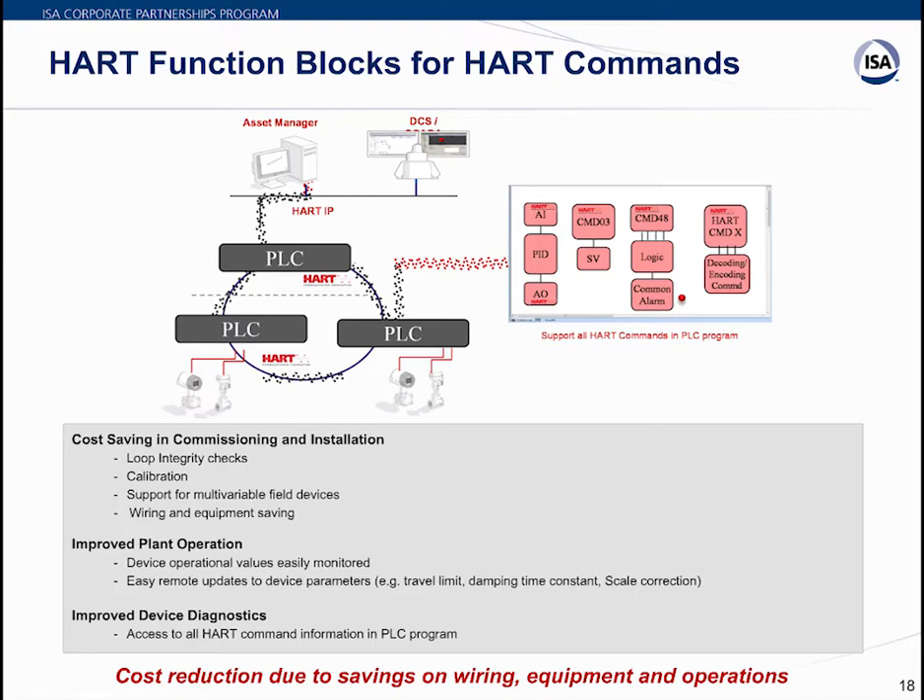Plant operations are significantly improved with HART command support in the PLC. It allows easy remote updates to device parameters — such as travel limits for control valves, damping constants, or scale correction on transmitters — without needing an asset manager or handheld terminal in the field. Device diagnostics can be fetched directly into the PLC program and used for interlocks or other logic. Overall, HART function blocks within PLC programs reduce cost and save wiring, equipment, and operations-related effort.